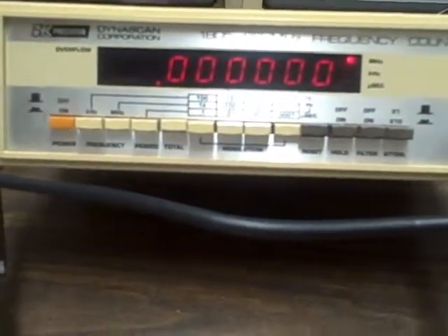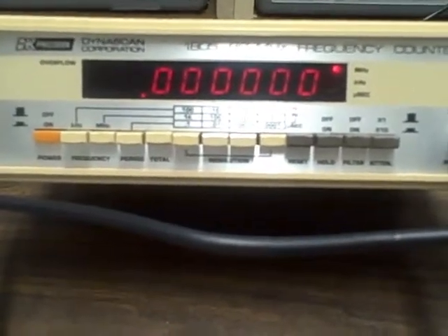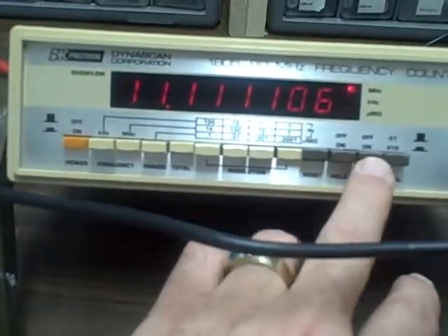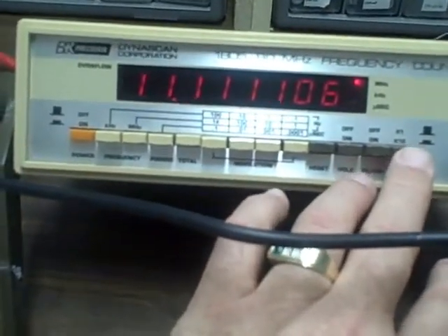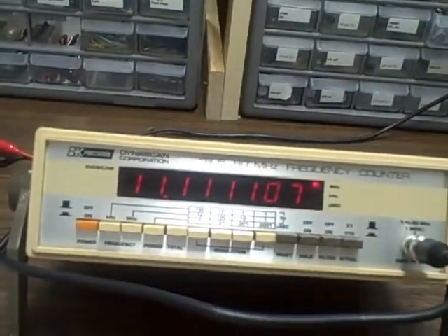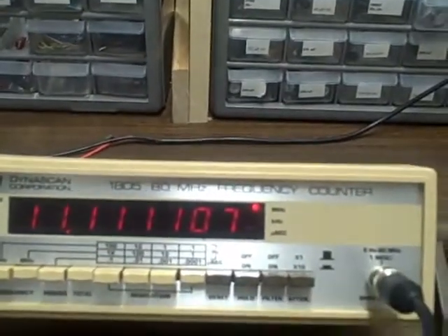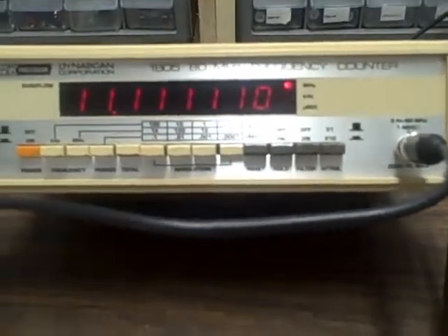There is a reset button for the totalize function, or you could reset the frequency and wait for it to count again — you'll wind up waiting 10 seconds and see the display pop back on. There's a hold switch to hold the display by hitting that button. We also have a filter switch to filter noise coming in, and an attenuator switch that allows handling higher-value signals.